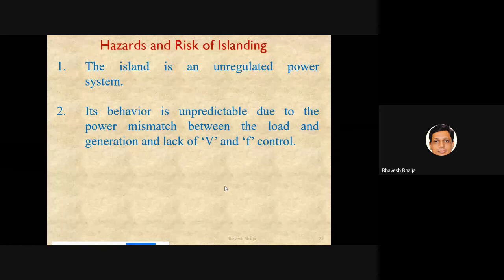And if there is no control of voltage and frequency, then in the region where the island is formed, the loads that are already there and supplied by the DG may have equipment with certain frequency and voltage limits under which they operate safely. If there is no control of voltage and frequency over that island portion, and it changes drastically, then whatever equipment is connected has a fair chance of being damaged.